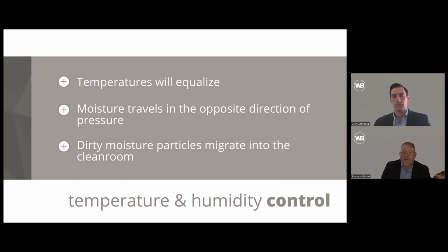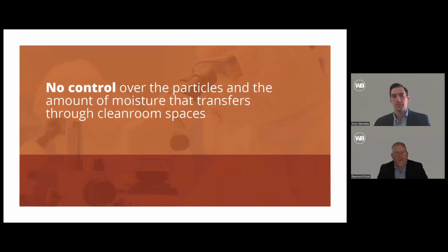To Drew's point, he just described how in a clean room, you want to maintain the cleanest space at the highest pressure and cascade air out in most cases. And when you do that, if you have a very humid environment on the outside, it will impact the humidity on the inside. So controlling the humidity, not just inside of the clean room, but outside the clean room can be important. Temperatures are a little easier to control, but you do need to make sure you understand how the moisture moves. And it's interesting, as we've talked about, particles move back and forth too. The dust and the tiny amount of these microns carry moisture and carry dust and carry viruses. They can actually carry things in the opposite direction of pressure as well. Not in large quantities, but you do have to understand that you have no control over that. And it's important to then try and manage it through all of the design practices we're talking about.